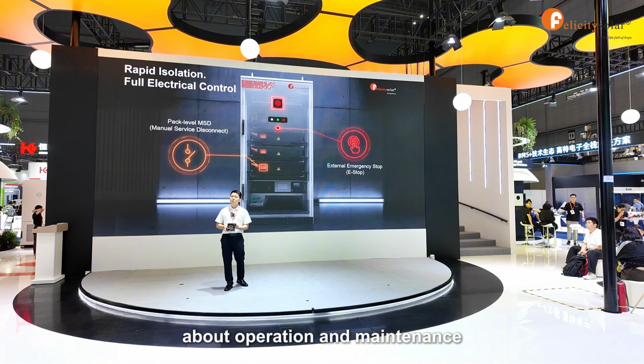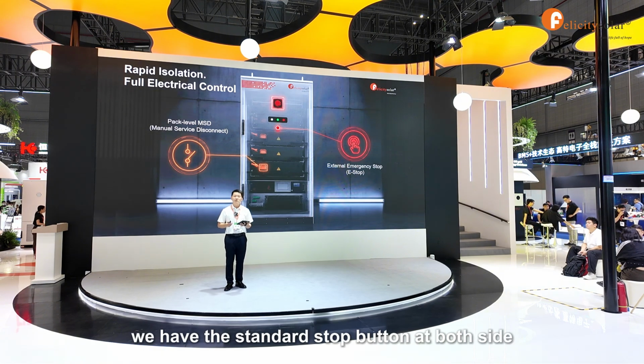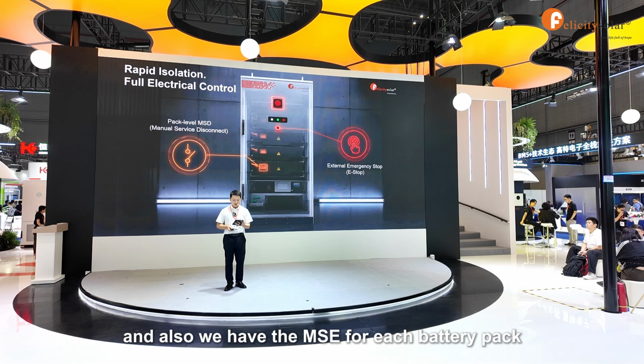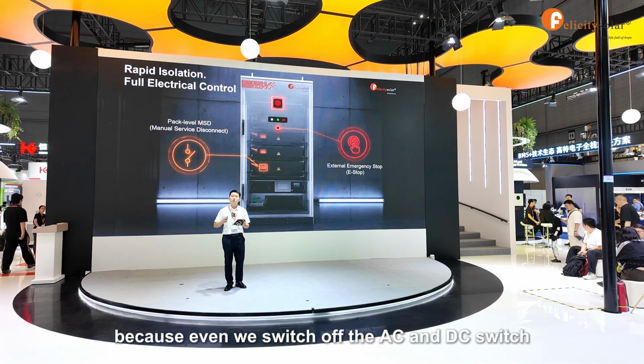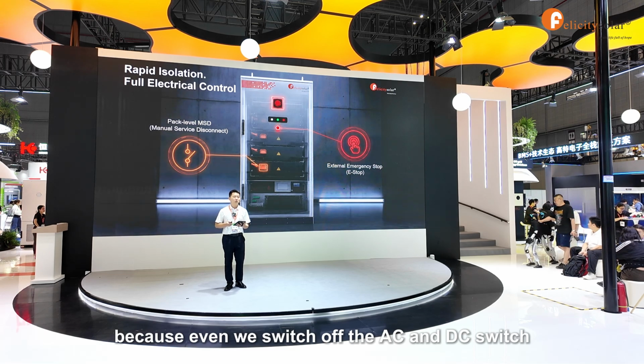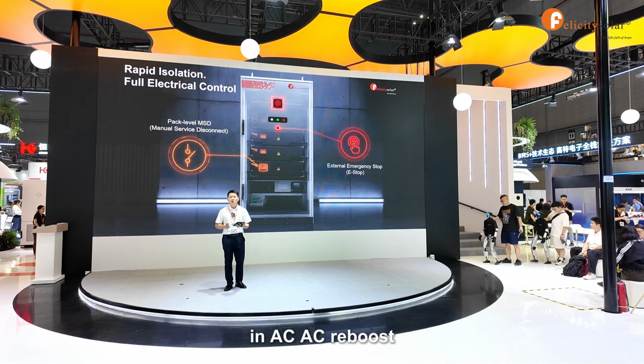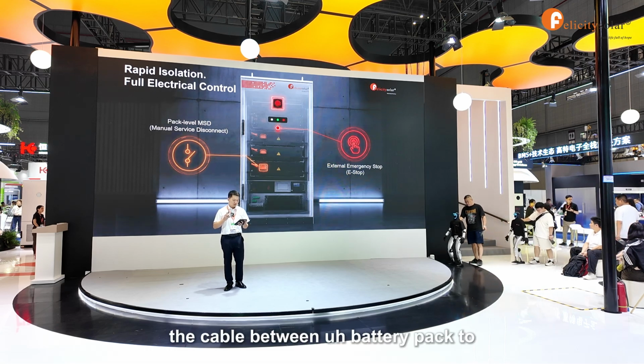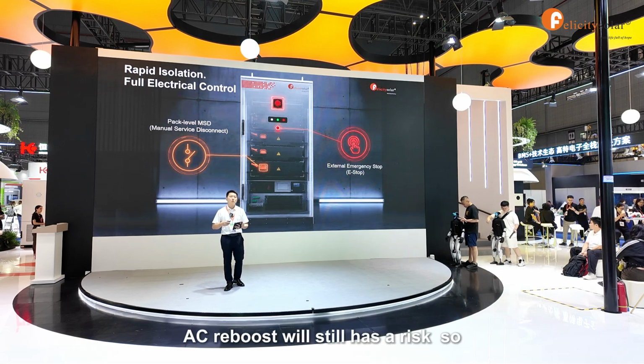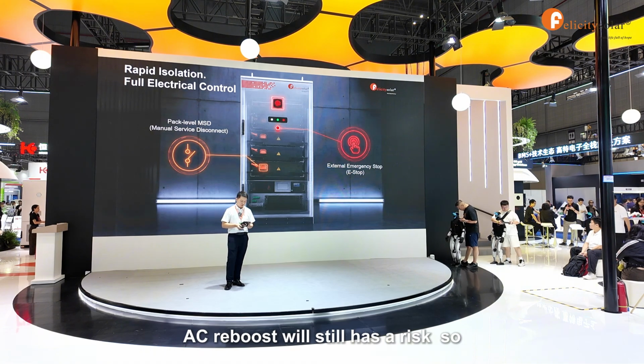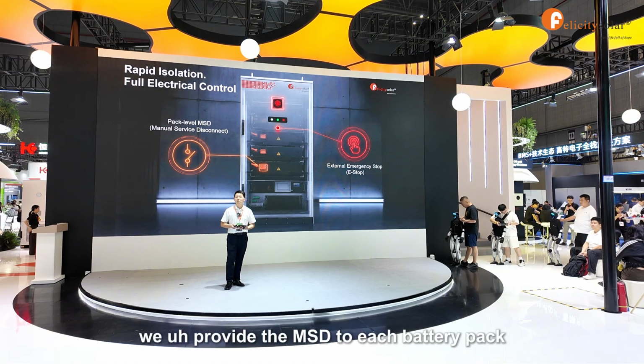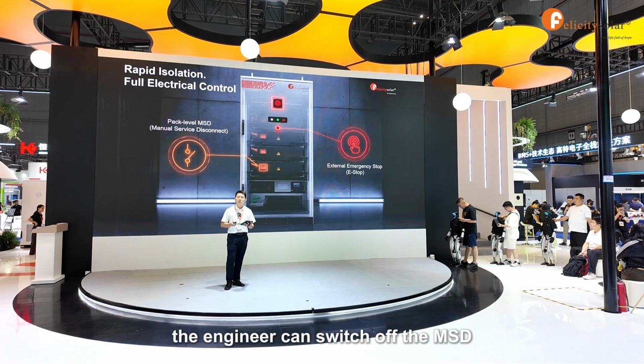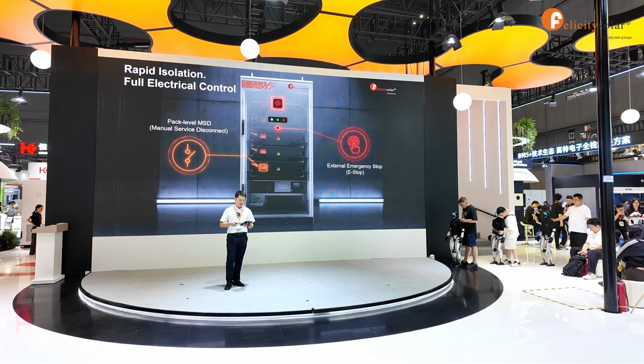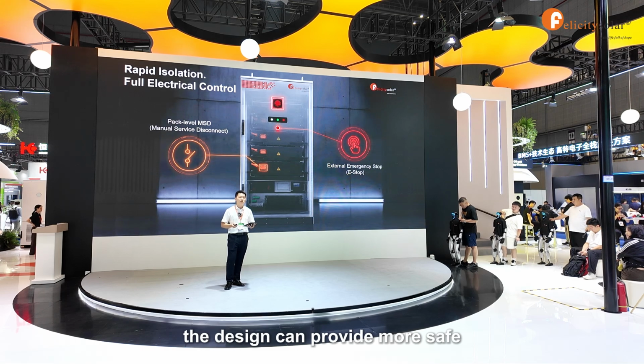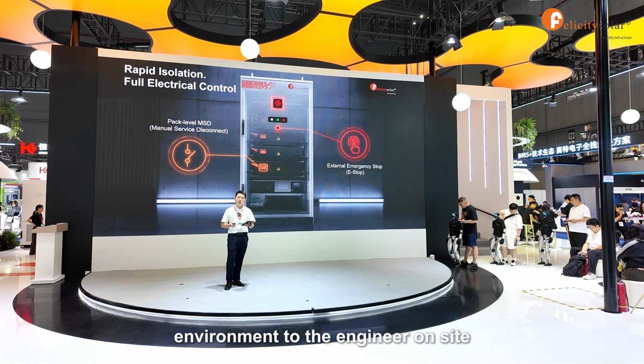About operation and maintenance, we have the standard stop button at the front side, and also we have the MSD for each battery pack, because even if we switch off the AC and DC switch in the HV box, the cable between the battery pack and the HV box will still have a risk. So we provide the MSD for each battery pack. The engineer can switch off the MSD. The design can provide a safer environment for the engineer on site.